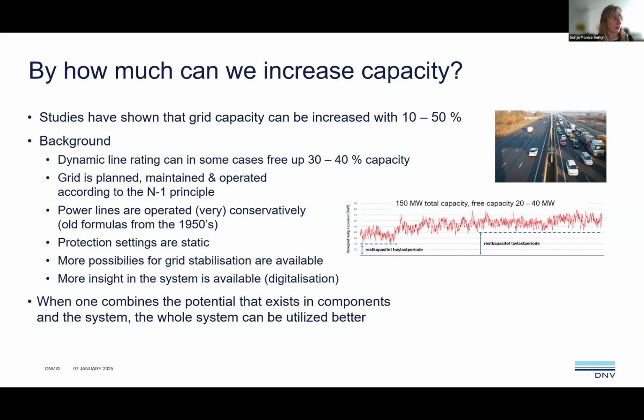So another thing that is possible, for instance, is dynamic line rating. And by that, we can free up 30 to 40% of the capacity. And in my opinion, that is mainly caused by the fact that the power lines are operated with very conservative formulas from the 1950s. So we have formulas from the 1950s that calculated how much a line will actually sag based on the current that is going through. And these formulas have never actually been challenged or updated. And now we have systems to measure very accurately both the current going through the line and also the sag. And then we see, hey, these formulas are actually wrong, or the wind is actually varying much more than just one parameter the whole year around. And in some cases, we can actually free up 30 to 40% of the capacity. And this is really a lot.